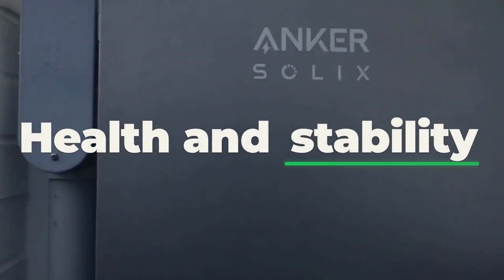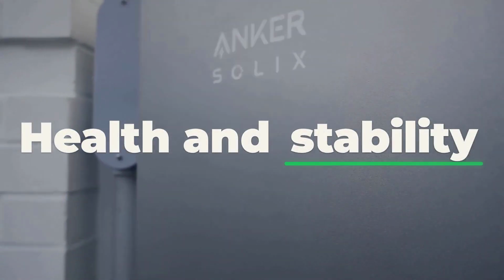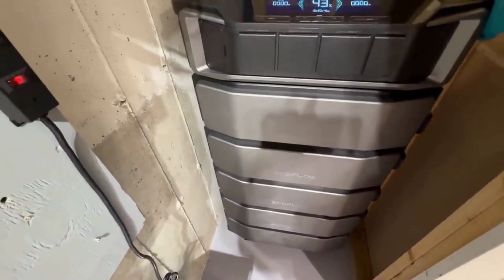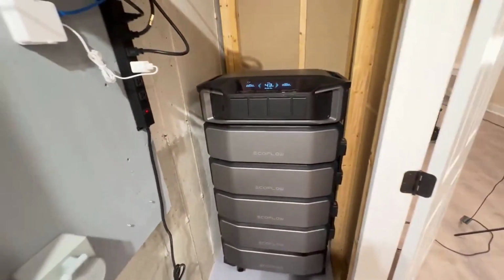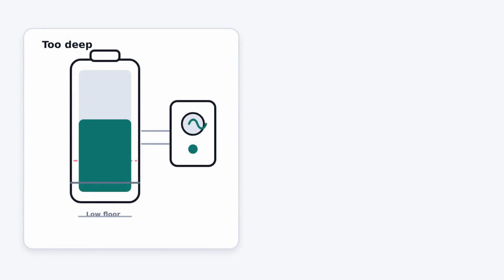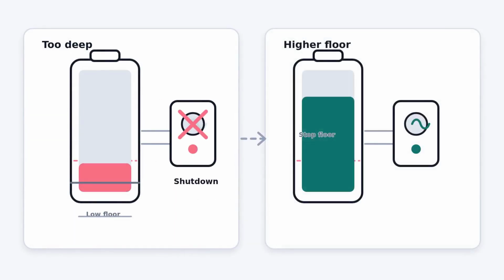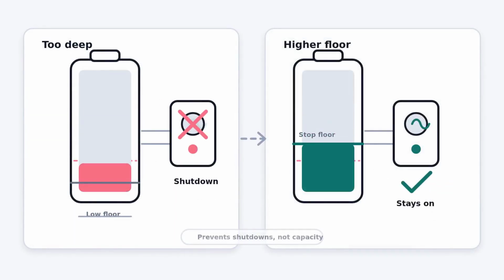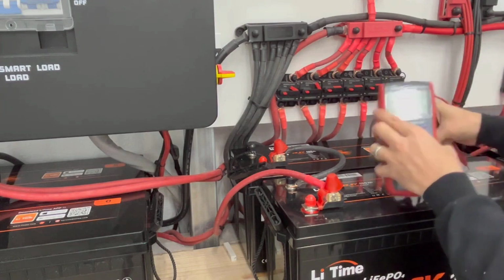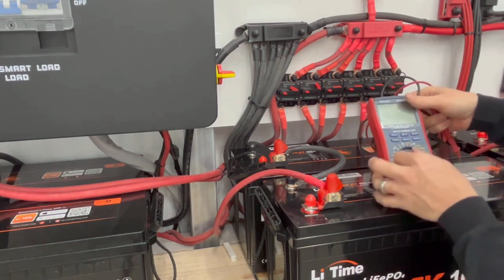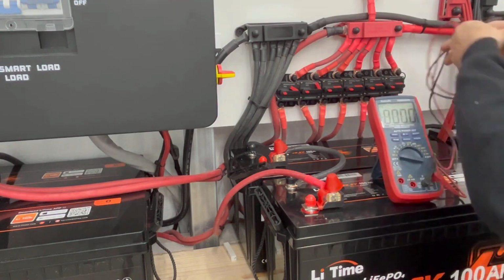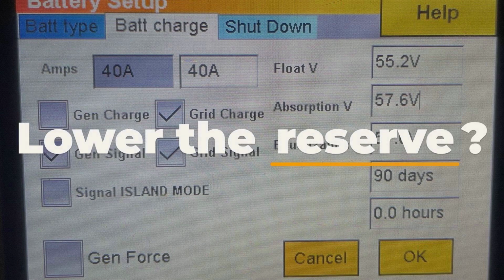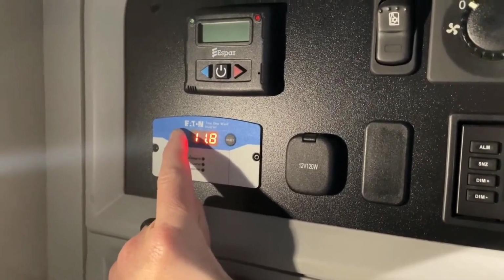What you are saving is battery health over time, system stability under load, and your backup reserve if the grid goes down. You are also eliminating the nuisance shutdowns that happen because the system ran too deep into the sag zone, which brings it back to the 40% problem. If your battery is tripping at a displayed 40%, the instinct is to lower the reserve so it can go deeper. That is the wrong move.